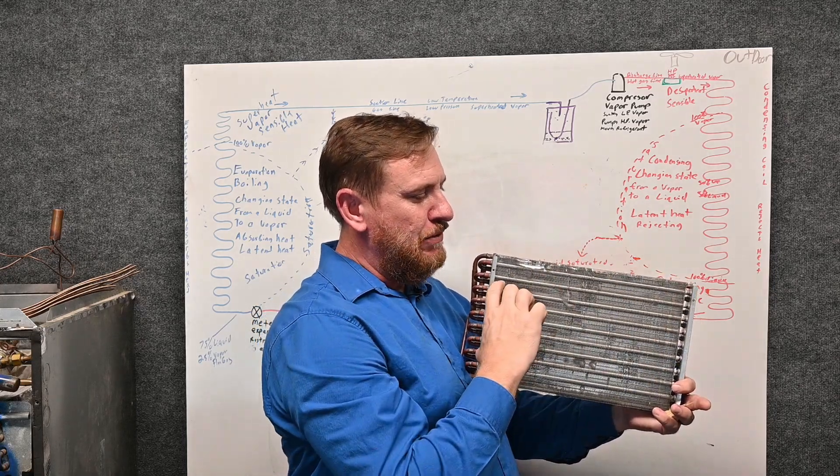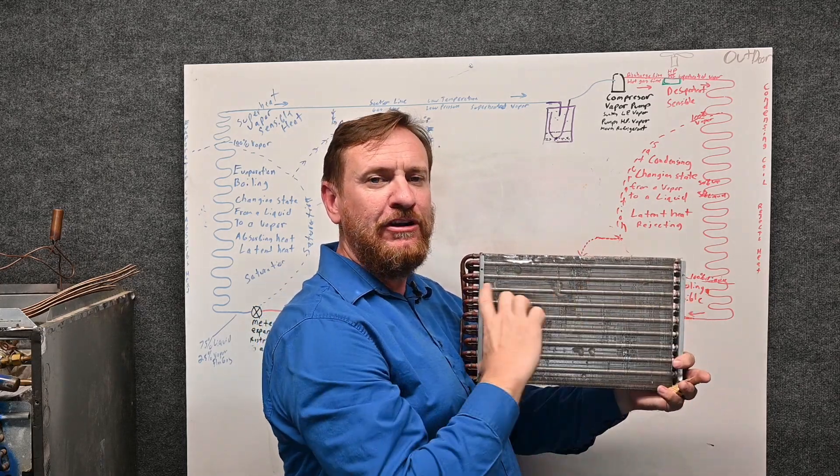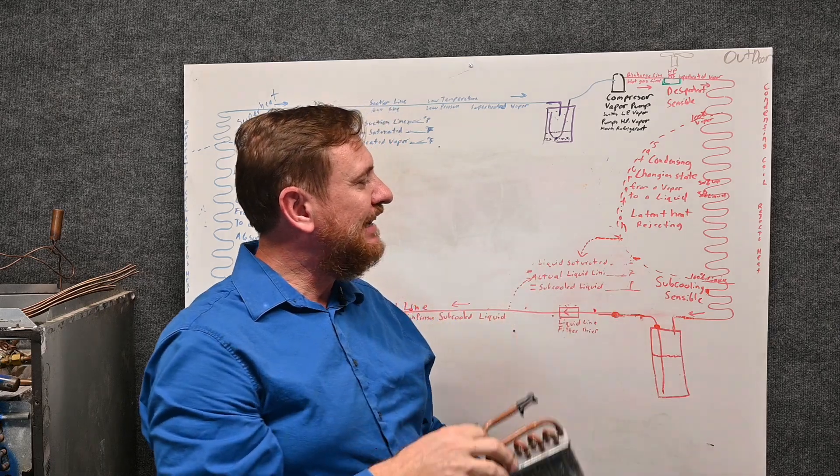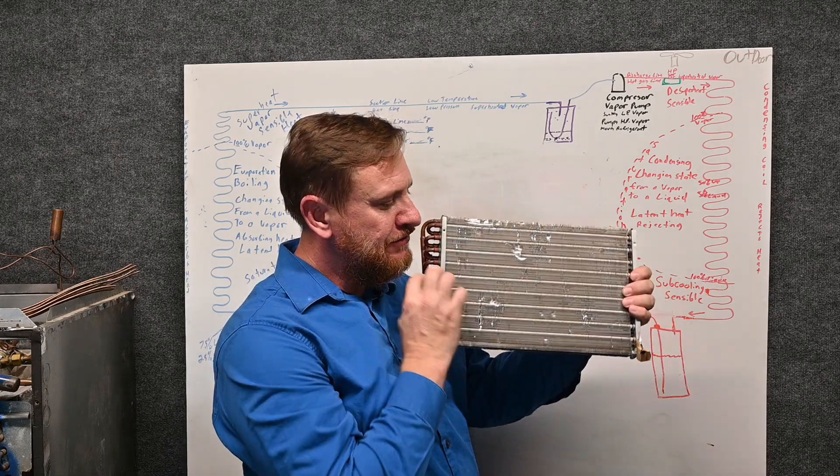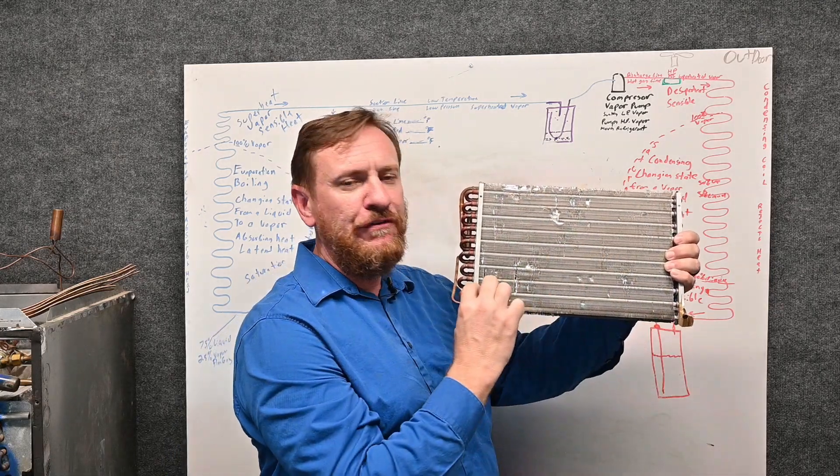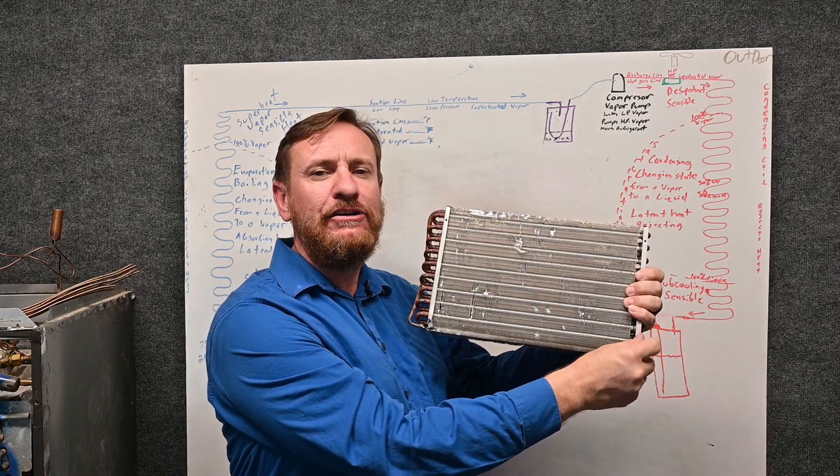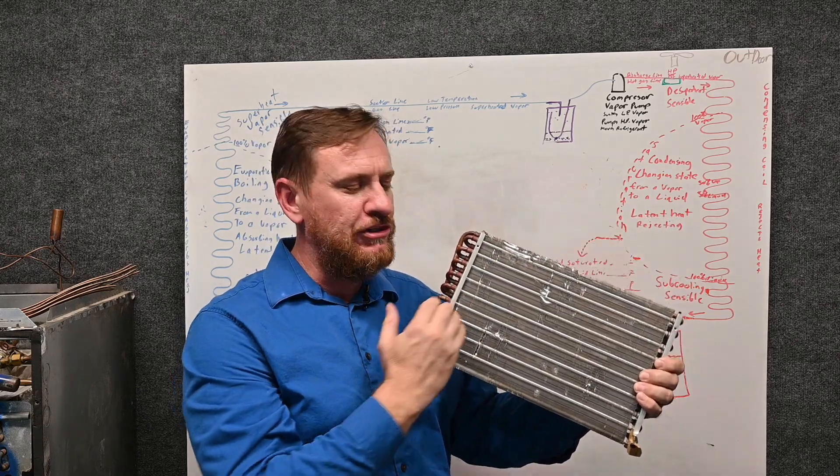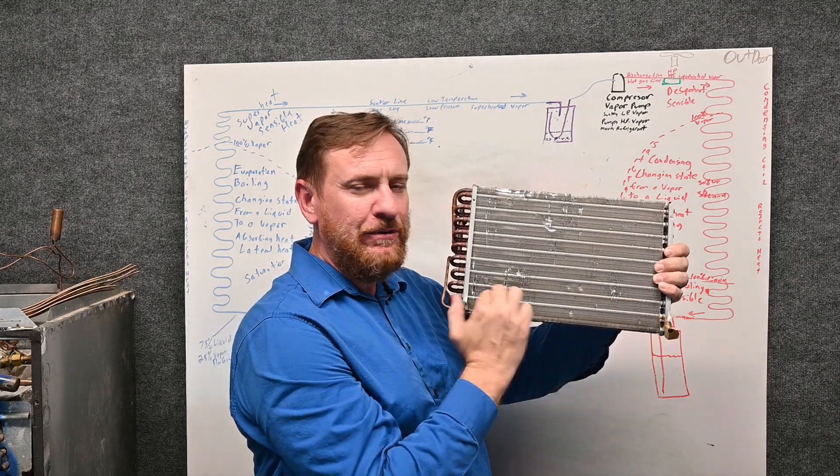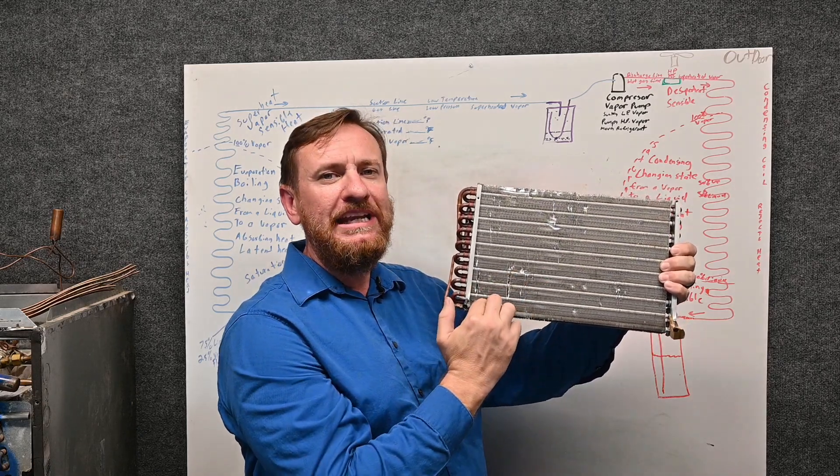We de-superheat it, we condense it—change it from a vapor to a liquid—and then the very last thing we do is we subcool that liquid. We can measure this now with the thermometer. So the last little bottom row of this condenser, approximately, is our subcooling, and it's taking it below a saturated temperature. Here it's 100% liquid, and then we subcool it even more. We take even more sensible heat, and you can measure that.